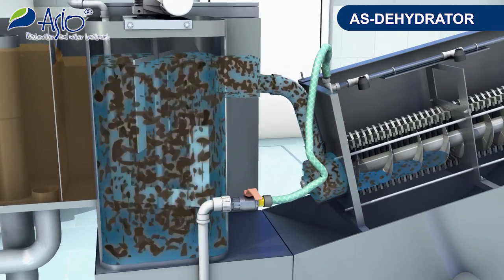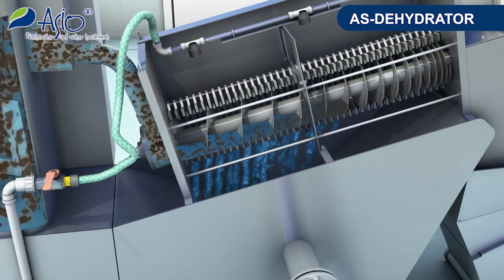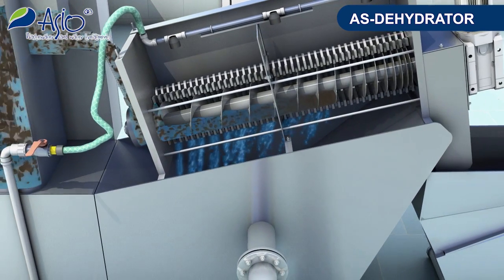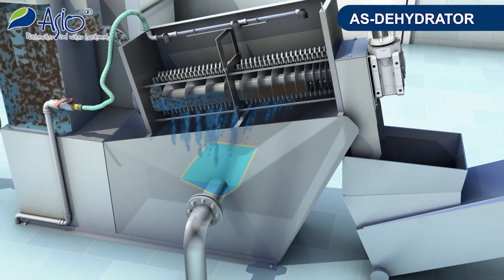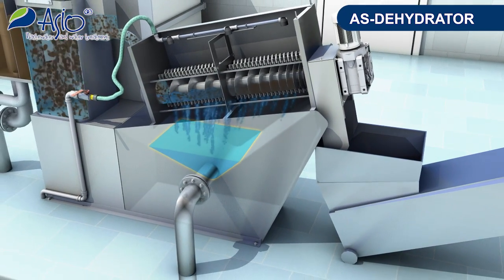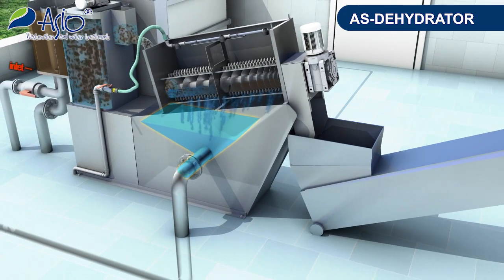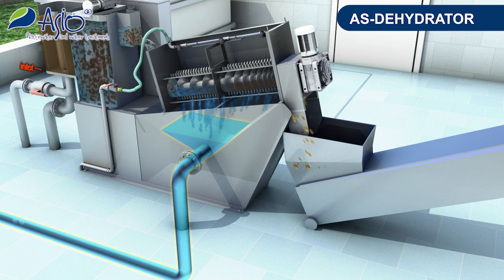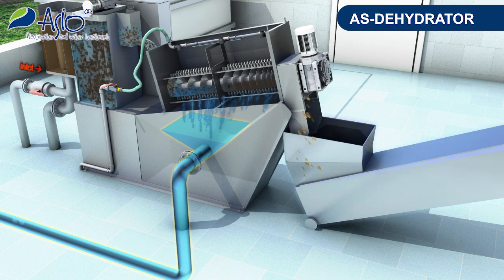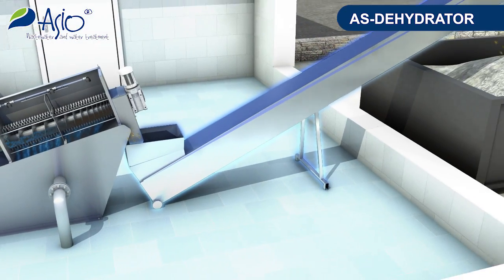The drum consists of a spiral conveyor enclosed in a tube in which there are alternate fixed and moving baffles. The spiral rotation moves the sludge to a thrust plate. At the same time, the water squeezed out of the sludge flows away between the baffles. The filtrate is brought back to the wastewater treatment process, while the dewatered sludge falls out at the drum end hopper with a dry matter content of usually 20% as a solid mass.